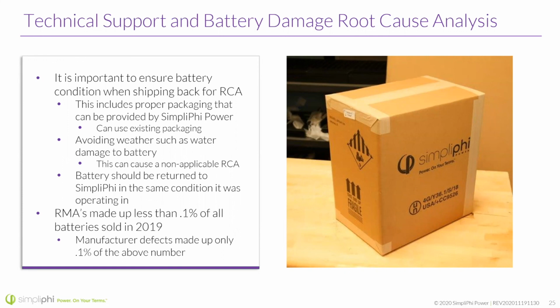I've definitely had batteries that were shipped back for analysis that had water damage on the way. We really have no way of determining if that water damage happened right at the time of shipping or if it happened a little bit before. Sometimes it might be obvious if it's wet when it comes to us, but again, that dries up pretty quick. Battery should be returned to SimpliPhi in the same condition it was operating in.